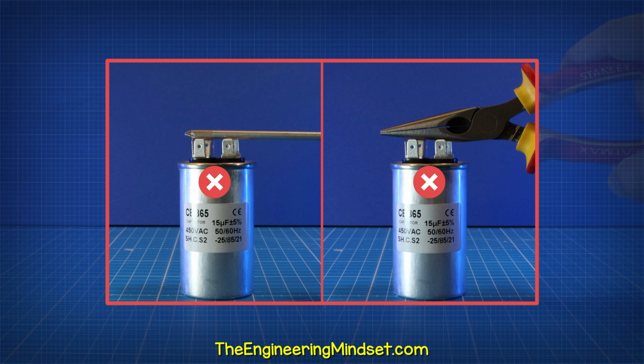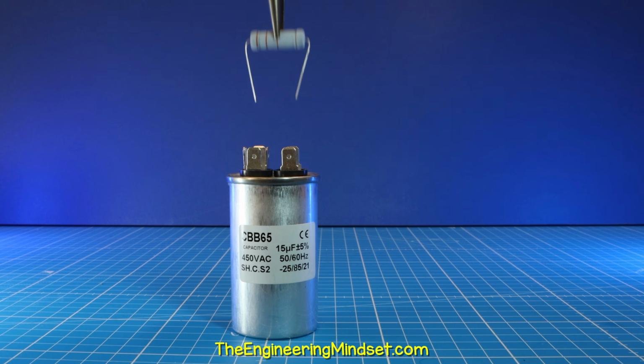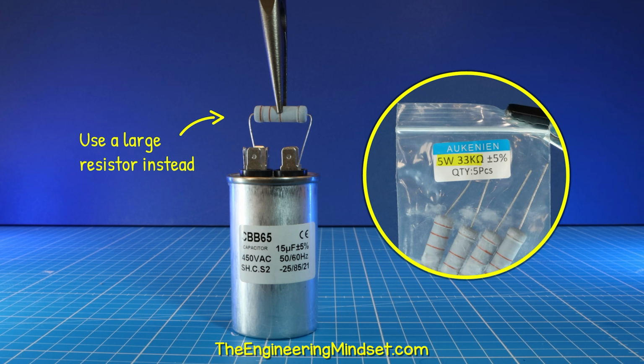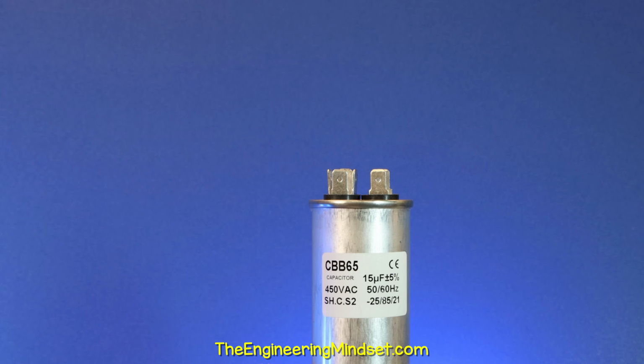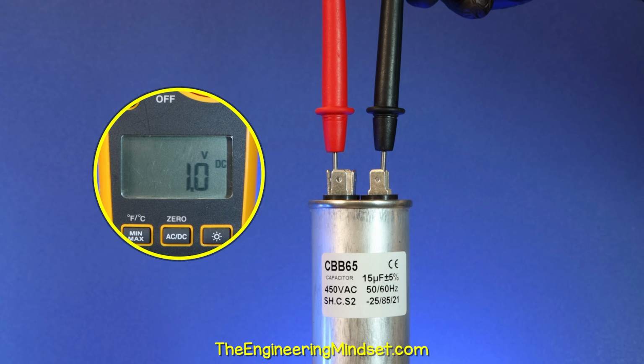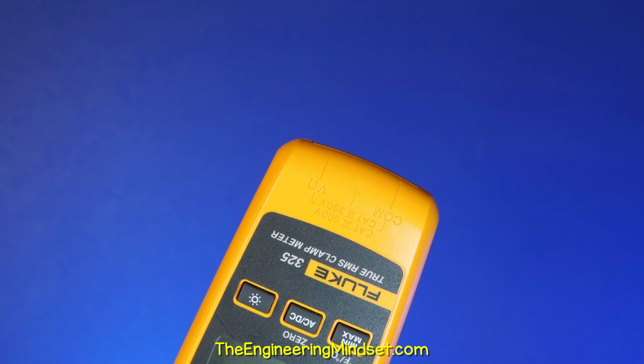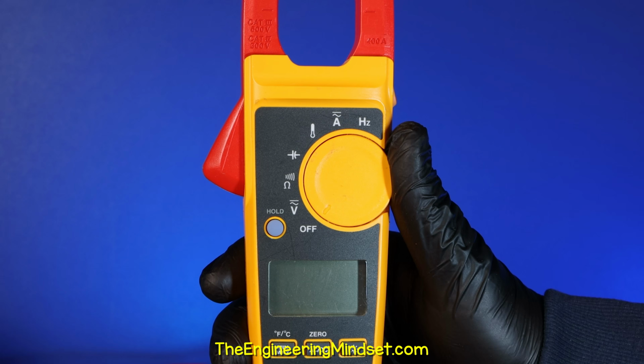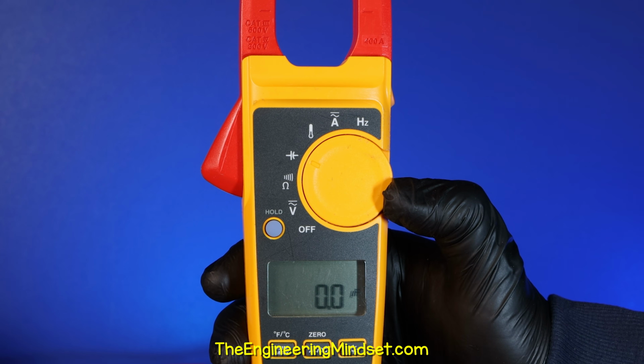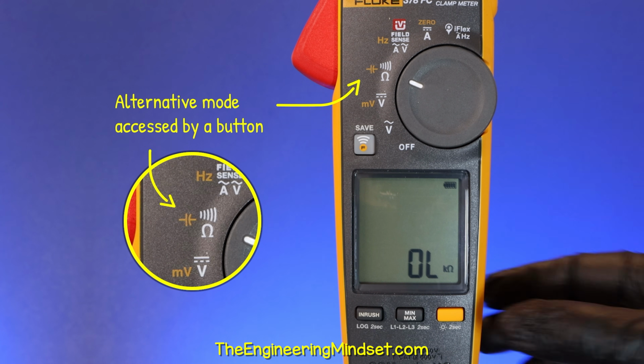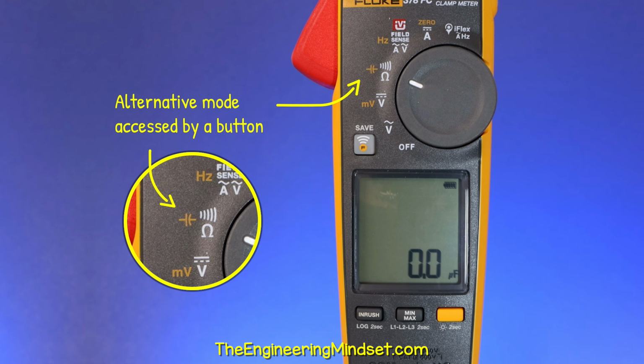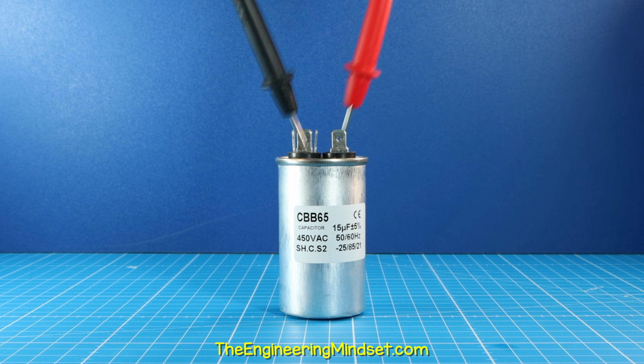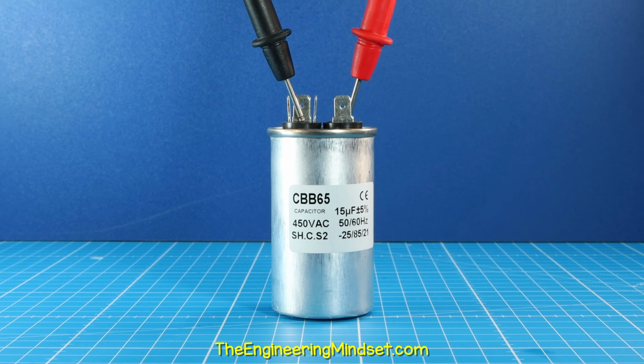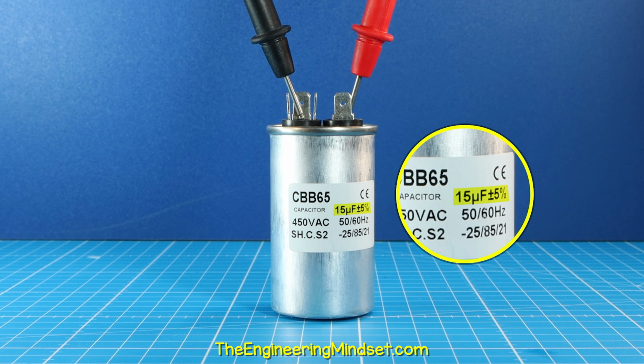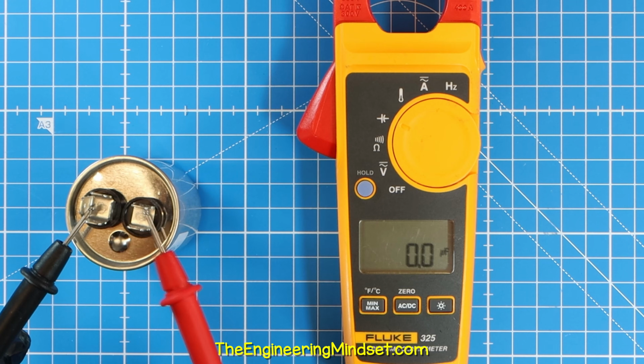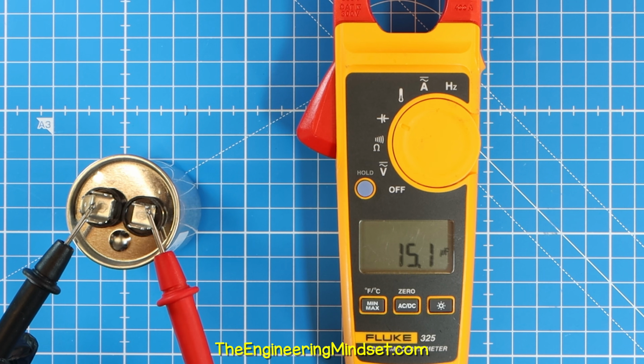Do not use a screwdriver or pliers to discharge them. Instead, use a large value resistor with a high wattage rating. You can use the voltage function to test if the capacitor is charged. To test capacitance, insert your leads and then select the capacitor function. This meter indicates that I need to press the yellow button to change the setting. Firmly place your probes against the terminals to take a reading. This one states that the reading should be plus or minus 5% of 15 microfarads. So this one is fine.